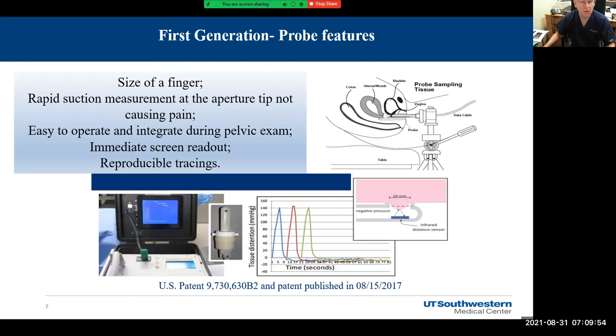If you look at the cartoon on the right side, you will see depicted the aperture at the end of the probe. The aperture is located superiorly. It measures 10 millimeters in diameter. A short suction, about 1 second in time at 150 millimeters of mercury, is applied to the anterior vaginal wall. The extent of vaginal wall downward deflection is captured by the infrared sensor located opposite the aperture.